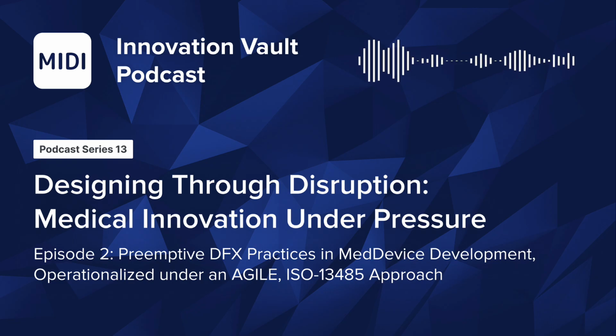DFT, meaning design for testability, is key to this verification, and DFU, meaning design for usability, is key to this validation. So basically, to put DFT and DFU into action, you need to not only consider the functional part of your device design, but also need to be considering from day one how you plan on testing the design and how you plan on validating it. This can end up influencing your approach at both the proof of concept level, prototyping level, and production level.